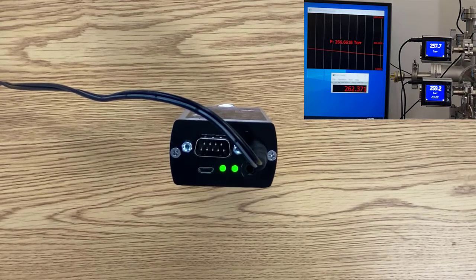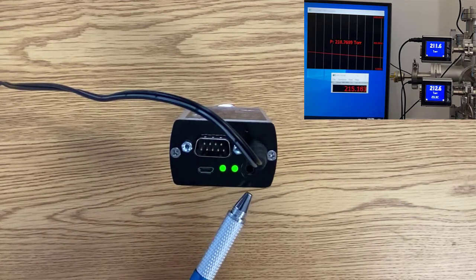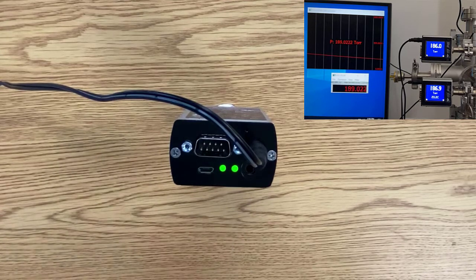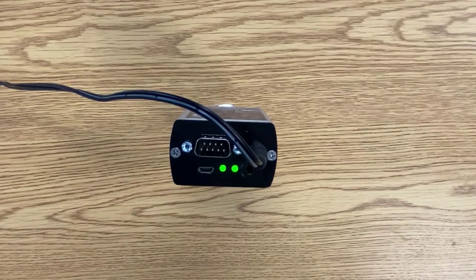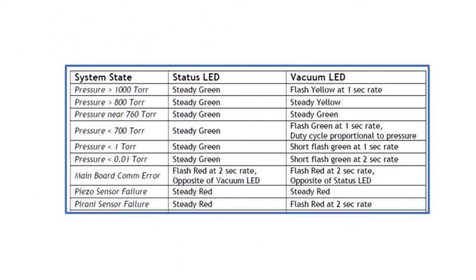In addition to the USB connection, we also have an RS-232, RS-485 port. And finally, I want to mention these two multicolored LEDs. Even if you don't order the touchscreen display, the LEDs are provided. The status LED tells the user about the health of the HVG. In short, green is good, and red indicates that the unit needs to be serviced. The vacuum LED tells the user about the pressure in the system.